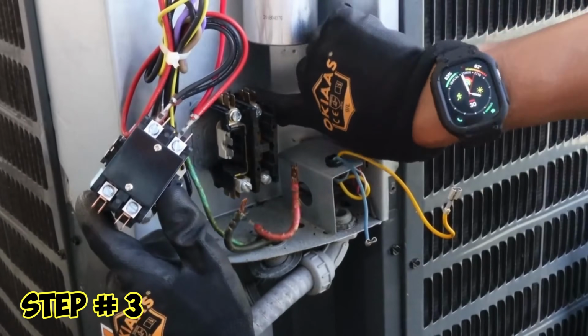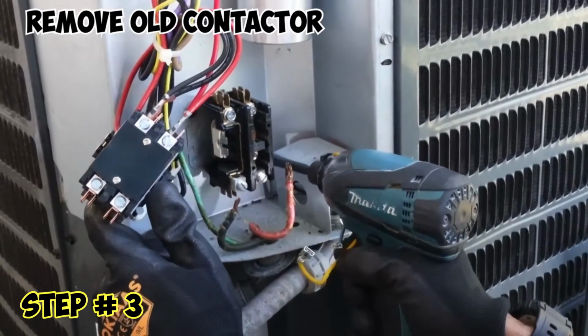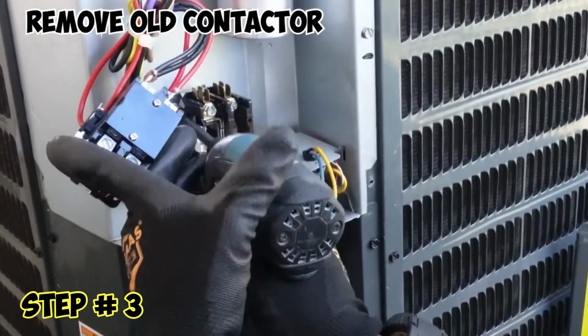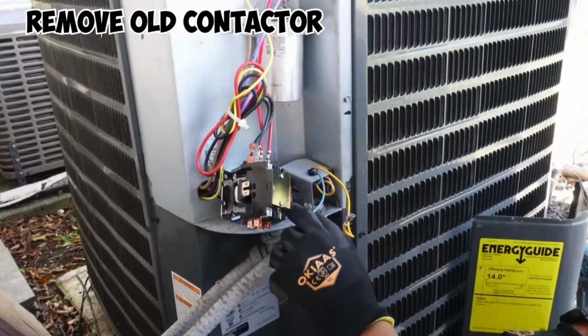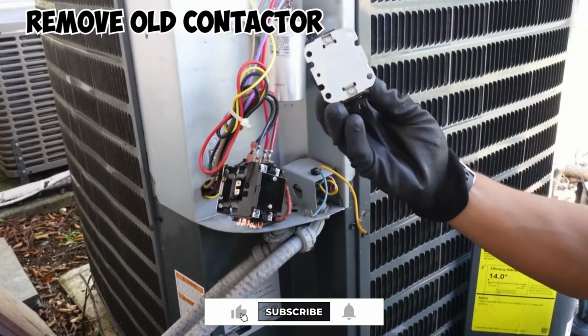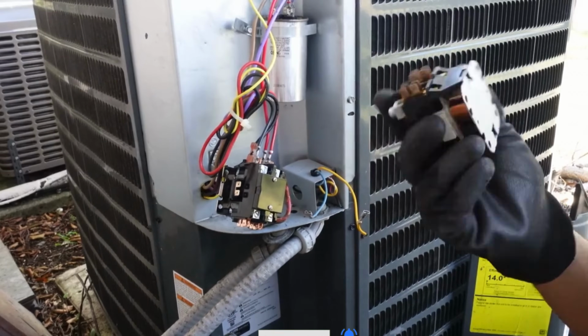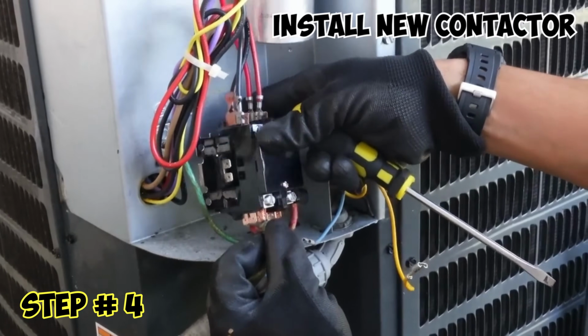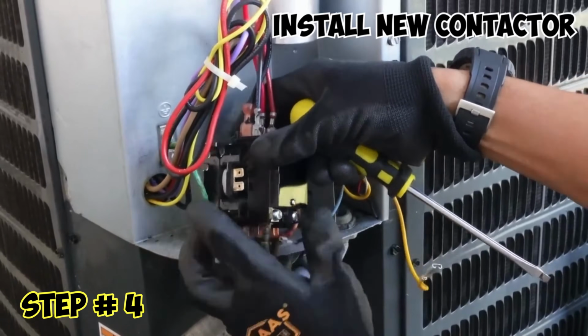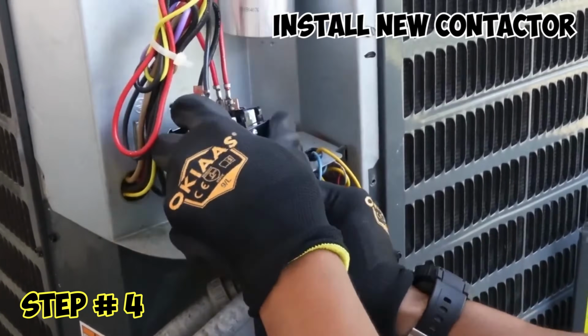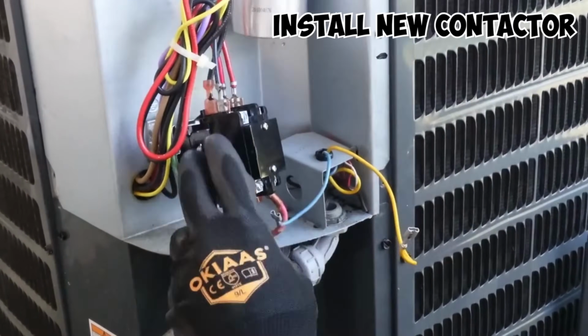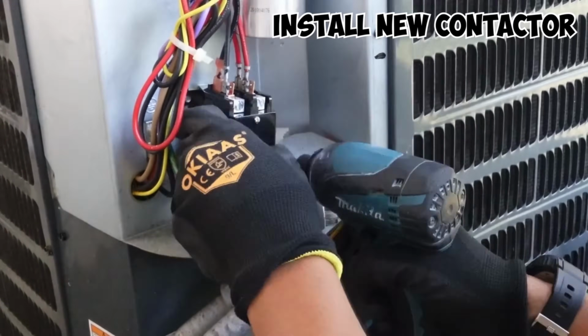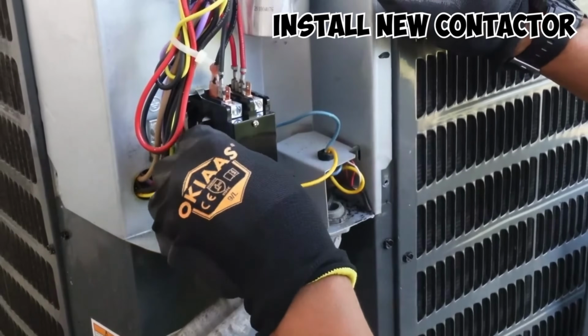Now, the next step is you want to remove the screw that's holding the old contactor in. Typically, it's a single screw. You might have 2 screws, but you may have 1 screw depending on the scenario. Just loosen that screw and the old contactor should come out. Next step is you want to secure the new contactor and screw it all in. If you didn't connect your wires like you did in the first step, now is the time to go ahead and replace all the wires and connect them all up.